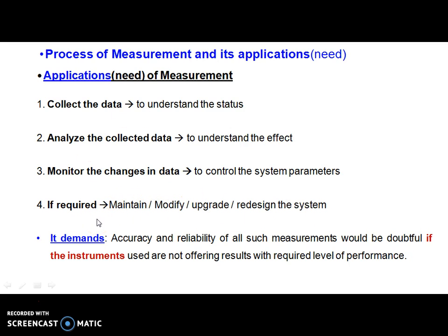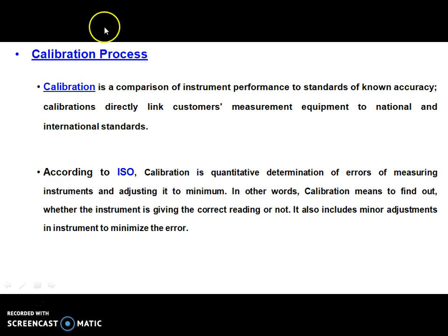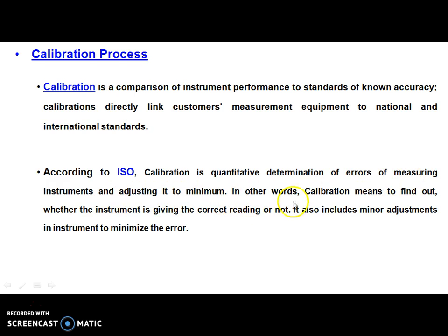These applications of the measurement process demand accuracy and reliability of the instrument that we use. The instrument should perform at the required level of performance, and for that purpose we need to analyze the status of the instrument. That can be done with another process called the calibration process. Calibration is the comparison of instrument performance under evaluation with a known standard of known accuracy. According to ISO, calibration is the quantitative determination of errors of a measuring instrument under consideration, adjusting it to a minimum. In other words, calibration means finding out whether the instrument is giving correct readings or not, and it also includes minor adjustments.